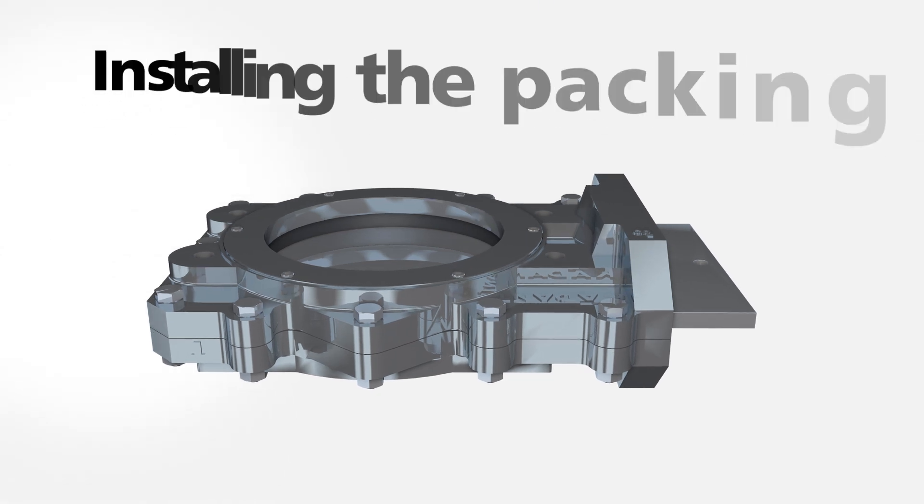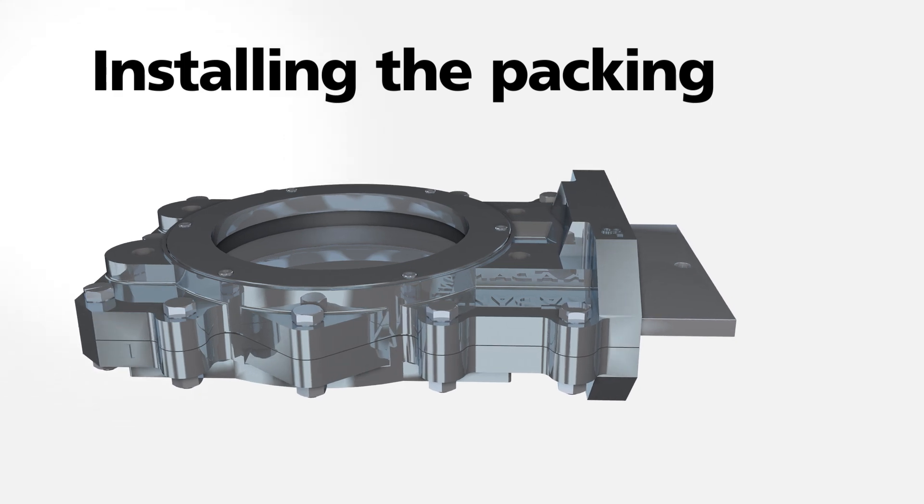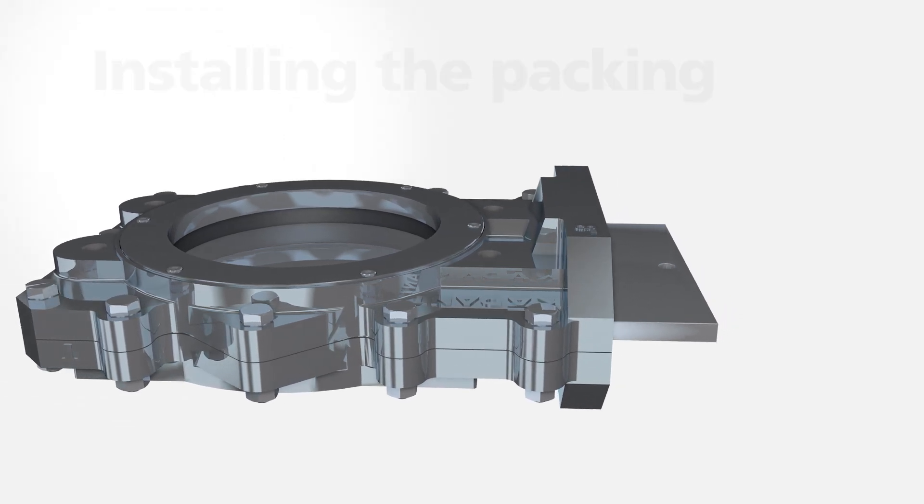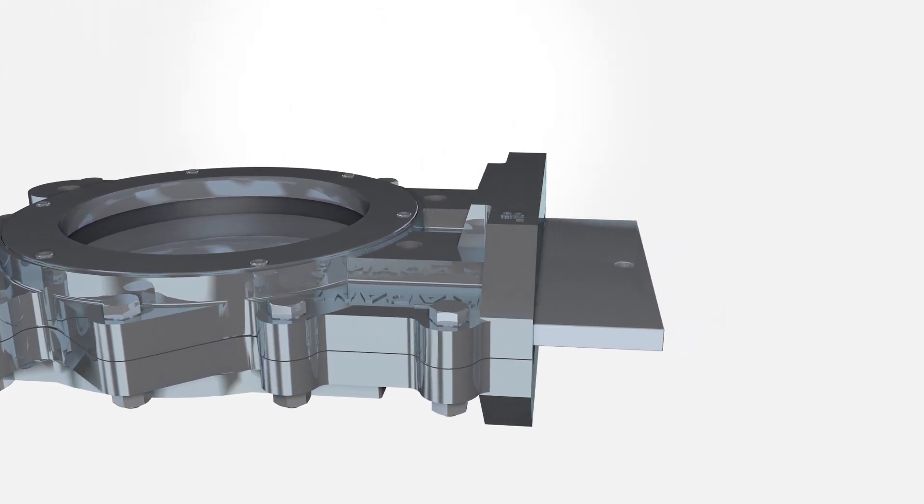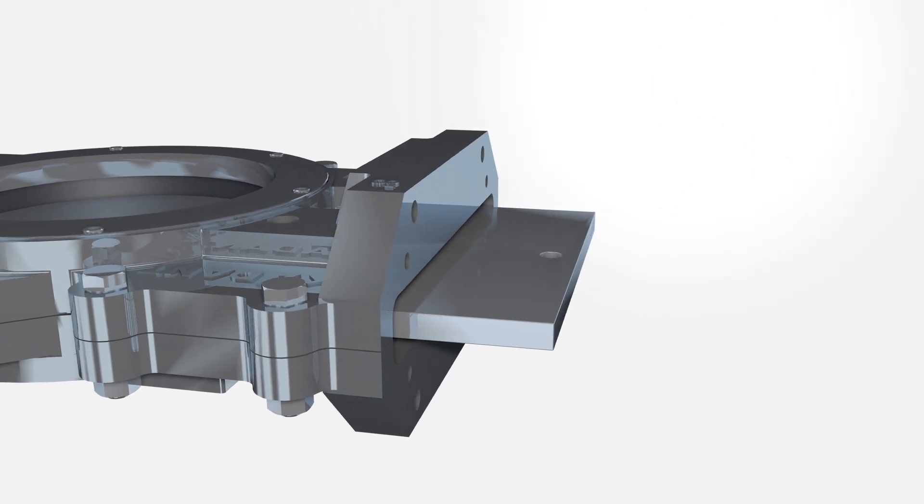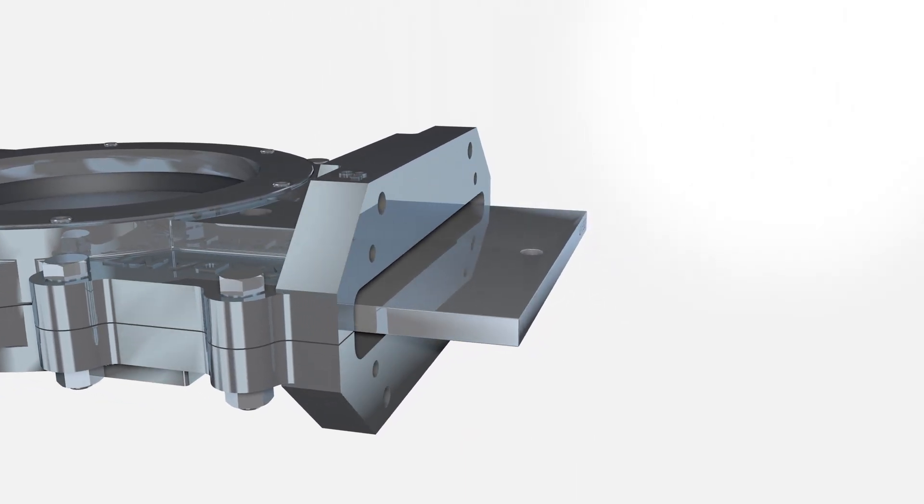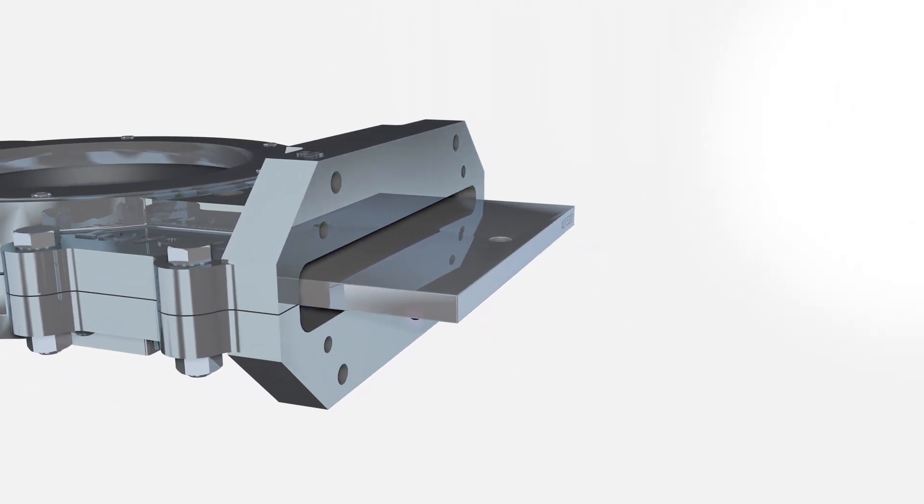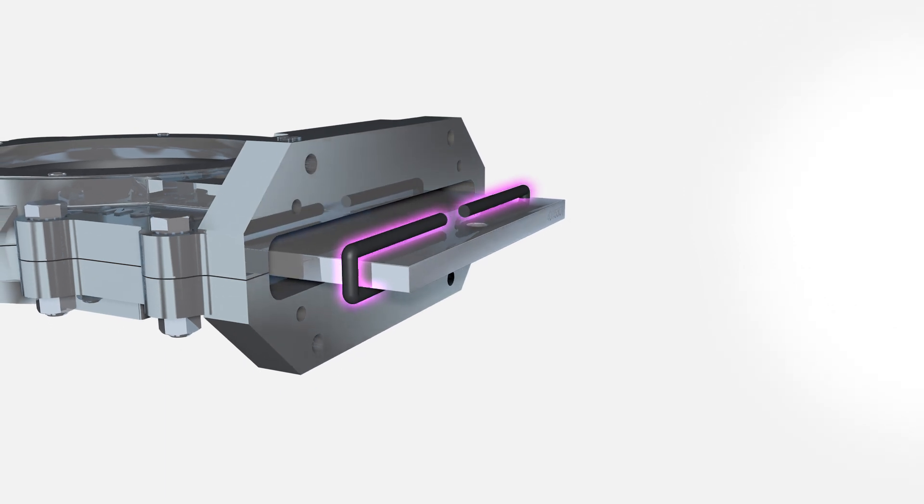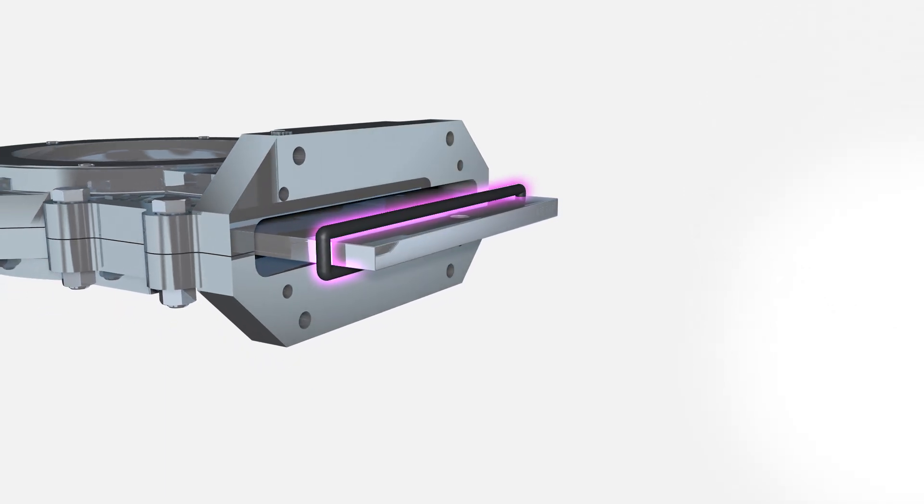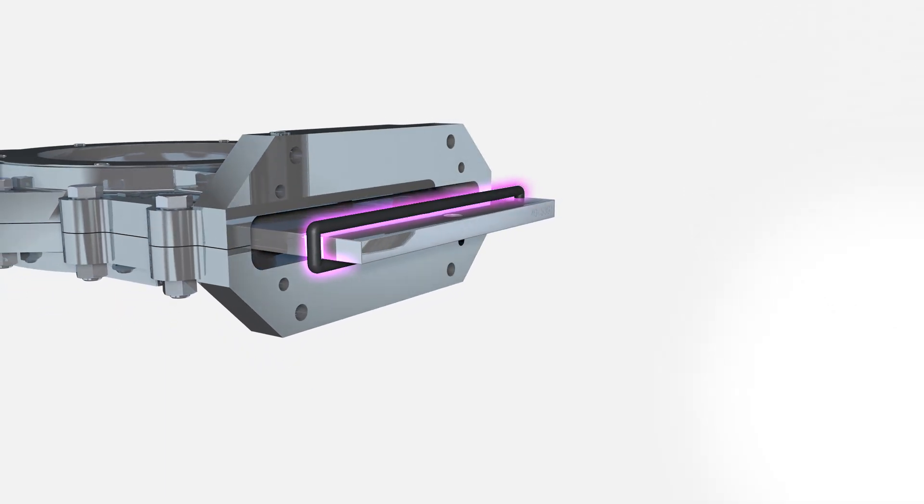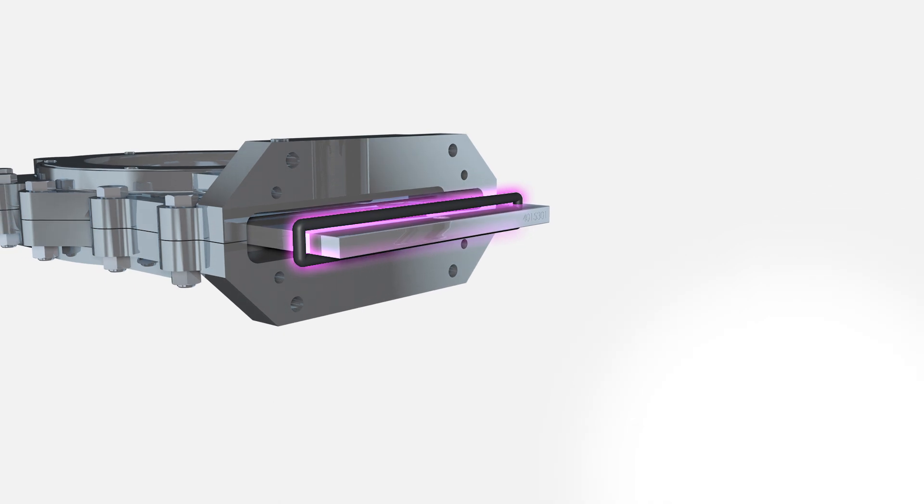Next, we'll install the packing into the packing gland. The packing seals the gate from the process fluid and is provided in the kit. First, form one ring of packing cord around the slide gate with the cord ends cut at a 45 degree angle, making sure the cut ends abut tightly.